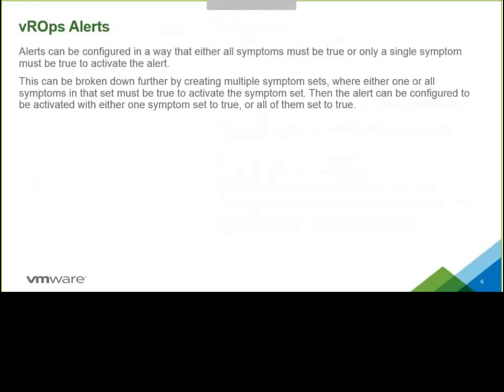And you do have an option to do conditional formatting in terms of whether you want all the symptoms to be true or you want a specific symptom to be true. So that's where symptoms come into the picture. And that's where you decide whether you want an alert to have multiple symptoms or just a single symptom. And what it helps you with is to detect or remove false positives, which can sometimes in a data center cause a lot of alerting, and people call it alert storms or flood or noise, in different terminologies in different regions, I would say.